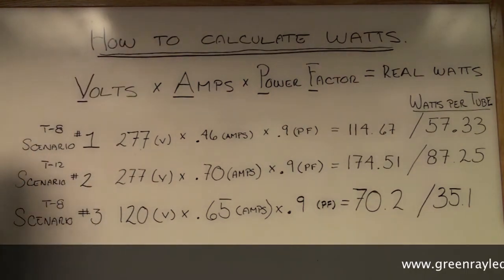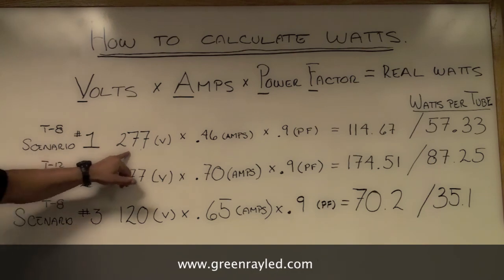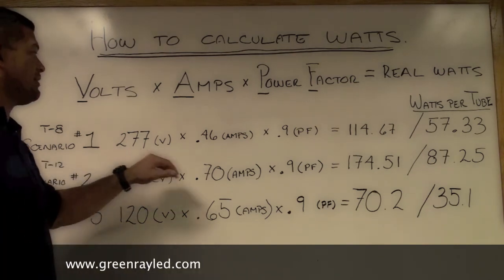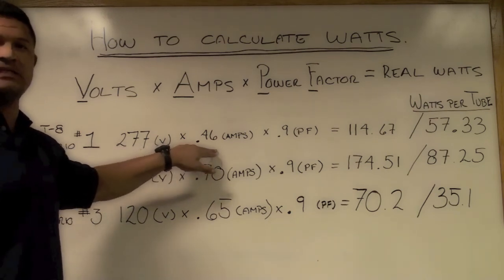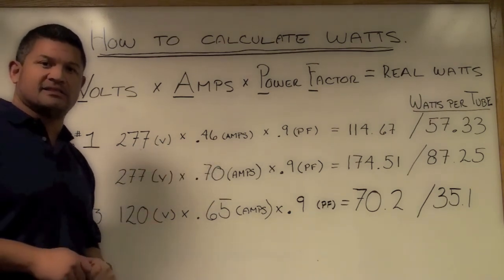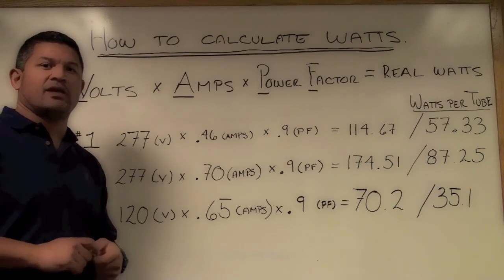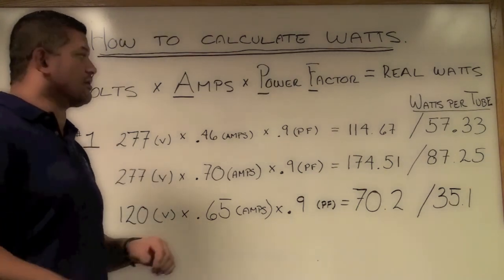Currently in the first scenario is what we have here in the office. We have a 277 T8 U shape in the unit. Our actual amps on the units are 0.46. This you can find on the ballast itself. Take a look at that and we can help with the calculation or you can give us a call.